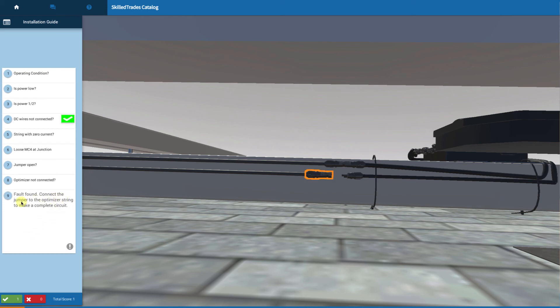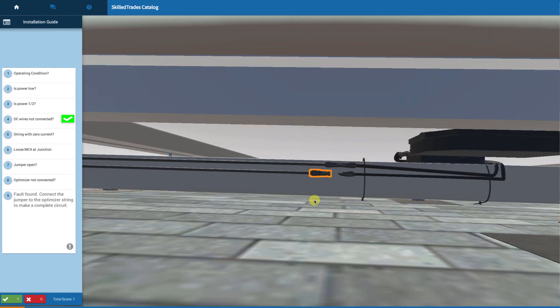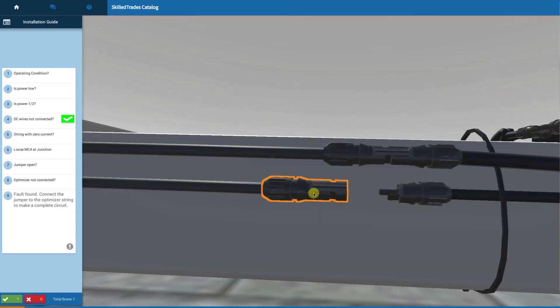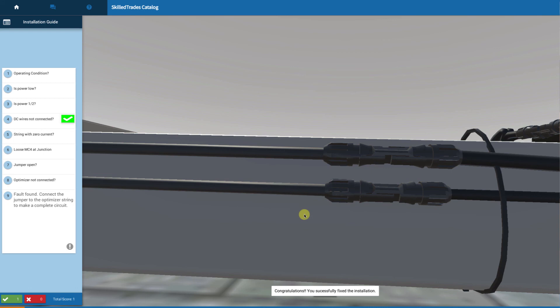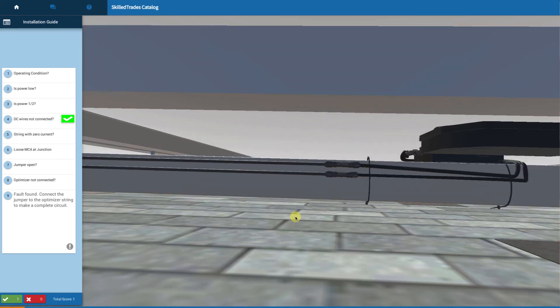Fault found. Connect the jumper to the optimizer string to make the circuit complete. I'm going to come in and connect them. You've successfully solved the problem. In this case, we found that there was a loose jumper connection that had to be fixed.